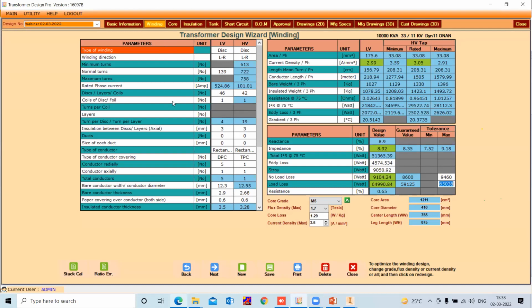You can see the column-wise parameters, second column for unit, third for LV winding detail, and fourth for HV winding detail. Now in this power transformer, both side windings are selected as disc winding, and it depends upon the ampere rating of this transformer, LV and HV side. Based on that, other options in this drop down will appear automatically, the suitable options. Thereafter, the normal turns, LV side, HV side, minimum, maximum, and normal turns. Here also the cells with white background are all editable. Using these cells, you may make your existing design also, like an existing transformer.